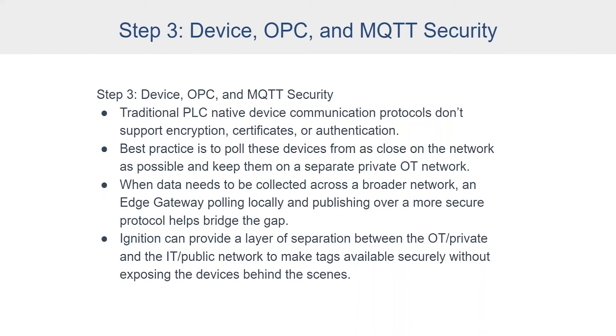Step three is device OPC and MQTT security. Traditionally, PLC native device communication protocols don't support encryption. They don't support certificates. They don't even support authentication. So best practice has been to poll these devices from as close on the network as possible, and these have often been kept on isolated controls OT networks. When the data needs to be collected across a broader network, you run into problems and have to do all this pass-through.